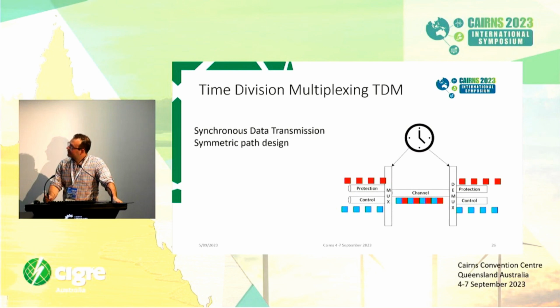So C37.94 is fundamentally a TDM protocol, or time division multiplexing. TDM is a method of sending multiple discrete signals over a single transmission medium, and each signal gets a fraction of the transmission medium's time to transmit its data. In this way, the higher speed channel in the middle here services the lower speed interfaces. This means the 2 ends of the communications channel must be synchronized to ensure that traffic in goes out the right connection.